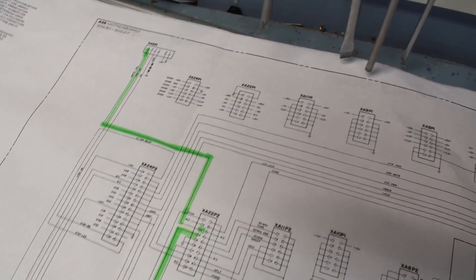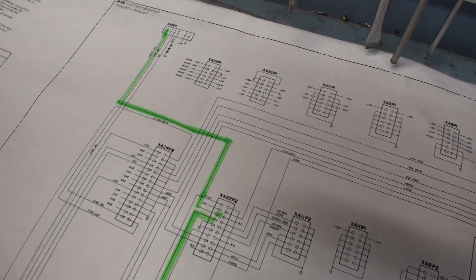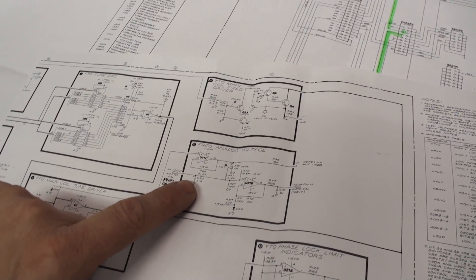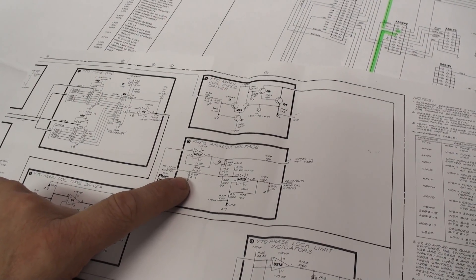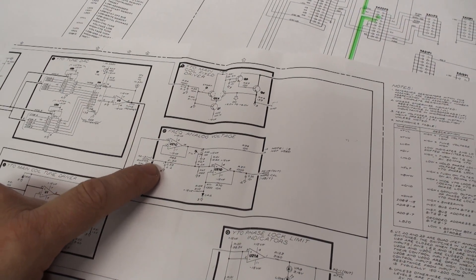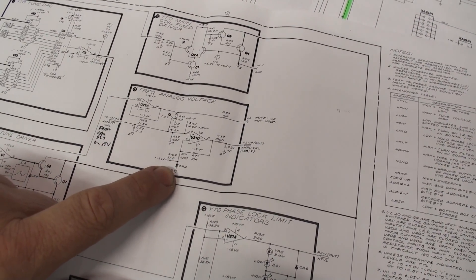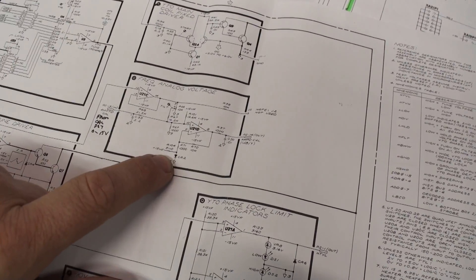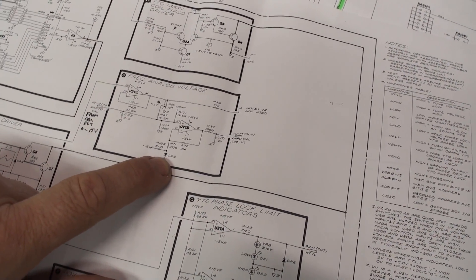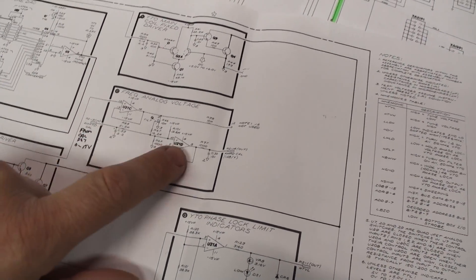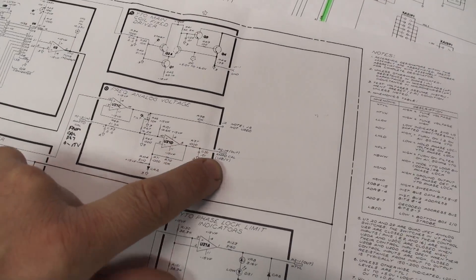So we're looking for plug 2, and it's on pin 3. And the A22, this is our first stop, is hopefully this board here, which I've printed out as well on A3, so it's a bit easier to see. Now what you can see is quite a straightforward system here. It comes into this comparator circuit here, an op amp sort of thing. And there's our signal coming in here. You can see that the inverting signal here is held down by a, looks like a 15 volt reference. Well, 15 volts apply here. I'm not sure the voltage of this zener diode. And we're applying a variable voltage here from 0 to 15 volts. And what that will do is we'll adjust the level of this output here.